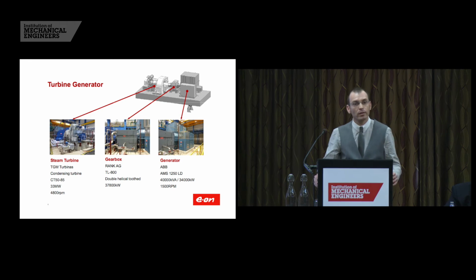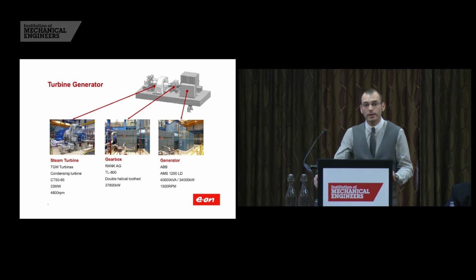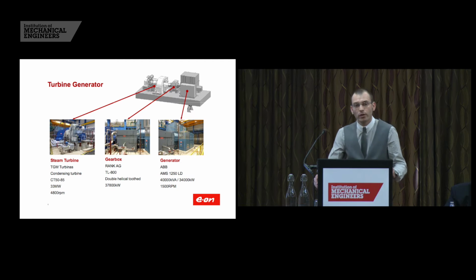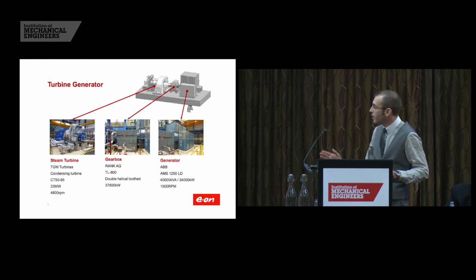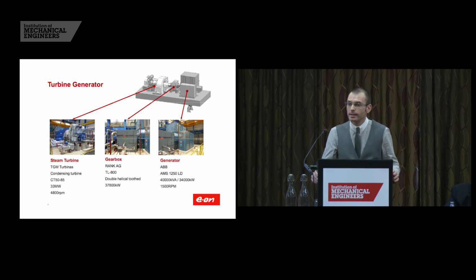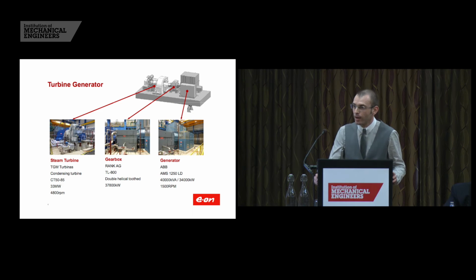The machine spins at 4,800 RPM, and this speed is transmitted through a reduction gearbox provided by Renk to the 1,500 RPM half-speed generator. The generator is provided by ABB. It's cooled via a closed-circuit cooling water system. Not only does this cool the generator, but it also cools the lube oil system, the main boiler feed pump, and the ash screws. TGM was also responsible for providing the turbine lube oil system, and the Balcke condenser, and the turbine control system, which comprises a Step 7 system for the steam turbine and a Siemens PCS7 for communication with the plant.